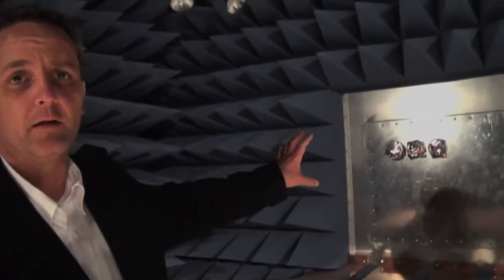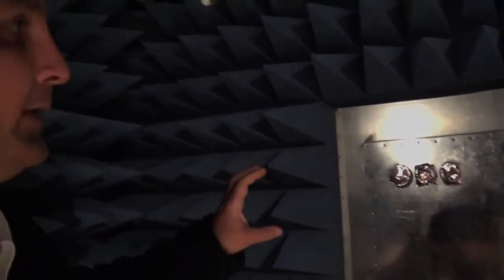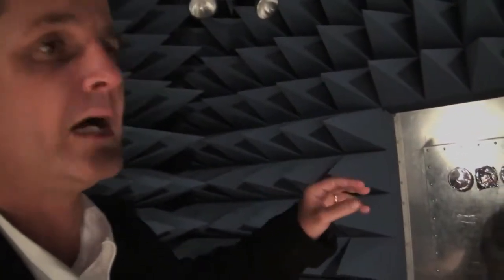One of the unique features of this chamber is this back panel that you see here. When not used, it can be covered with anechoic material, but when needed, this panel can be removed, which allows you access to the chamber next door. The benefit to that is it allows you to perform multi-platform testing.